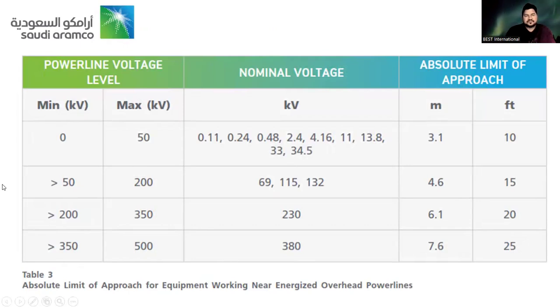Now, the power voltage levels, like a minimum, if it is 0 kV, I hope now you have understood what kV, kilovolt, is: 1 kV is equal to 1000 volts. So 0 to 50,000 volts, if nominal voltage is 0.11 or 0.24 kV, the absolute limit of approach is 3.1 meter or 10 feet.